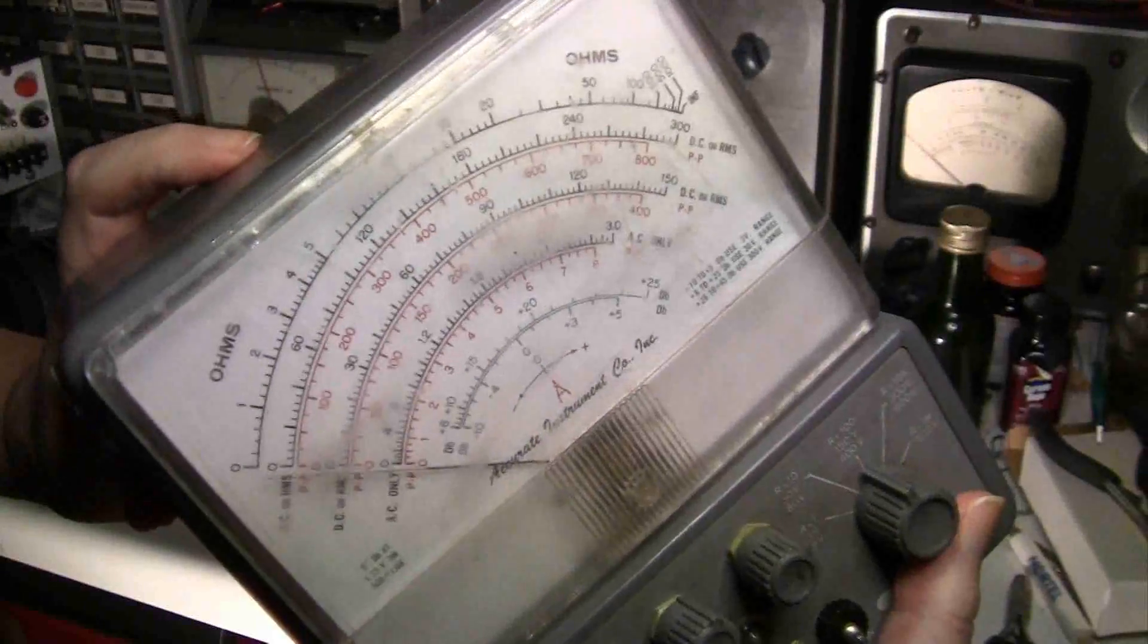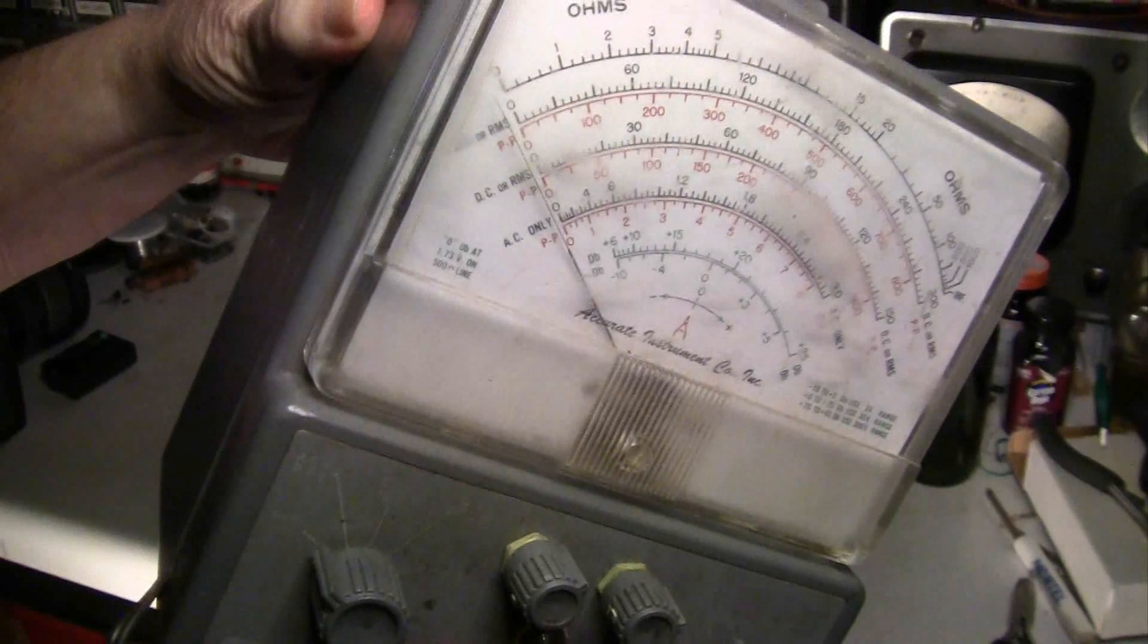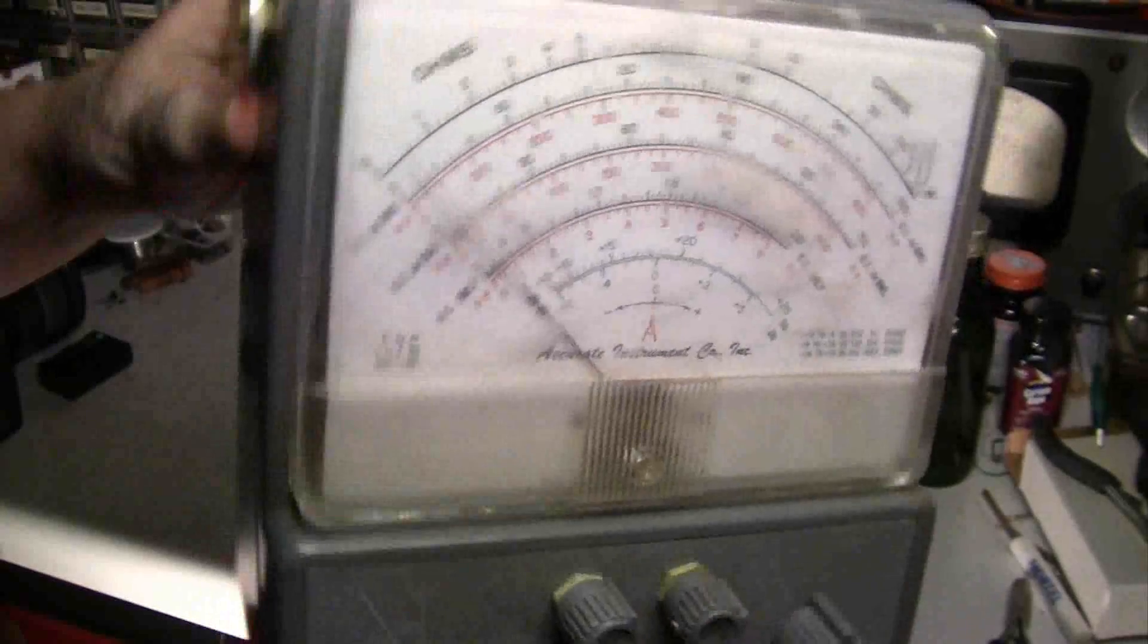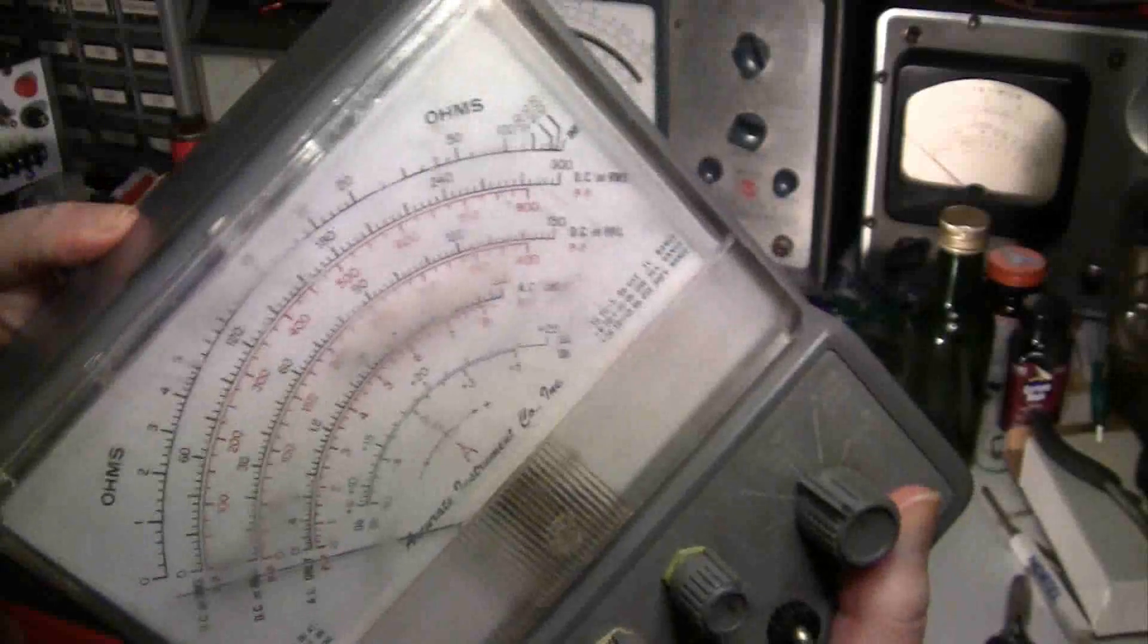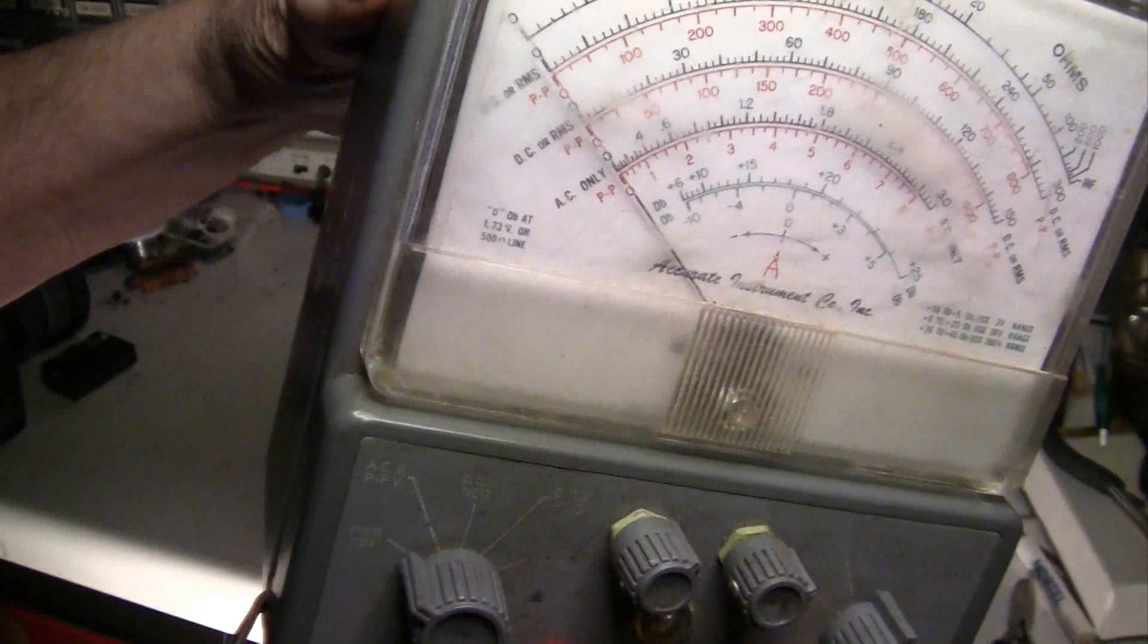And then the next thing I do is this. I'll take that meter and I'll quickly rotate it. And what I'm doing is I'm watching how that needle moves. Now here I'm going to slow it way down so you can see what I'm talking about. I'm looking for a very smooth motion when I have stopped rotating the meter, watching that needle go back to the zero position again. It's also important that the needle goes back to the same place each time.